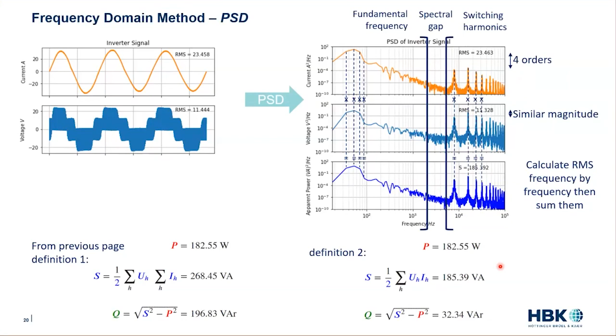So now by filtering out the harmonics, we can recalculate. Here's now showing us our voltage. Here's our current. We multiply them together. This is our power. And if we now use our definitions, our power is still 182, well, now 11, because we've lost a tiny bit of active power. Our apparent power is 187, so much, much closer to our frequency domain. And our reactive power, again, is very, very similar now to our reactive power from the frequency domain.